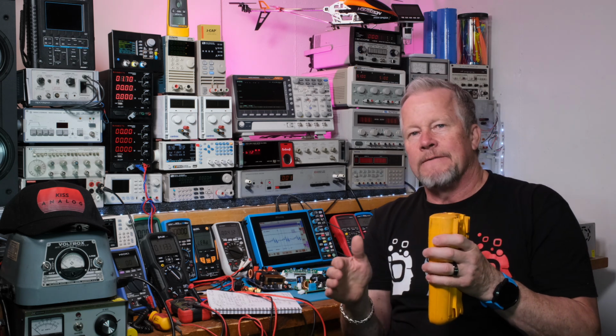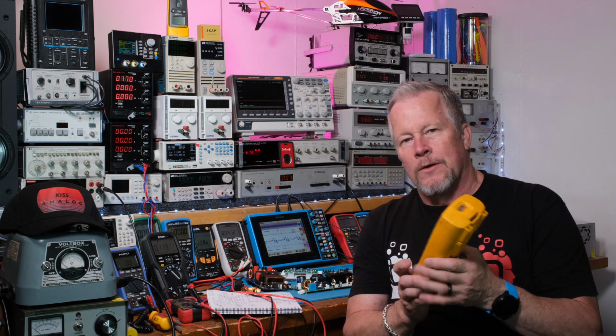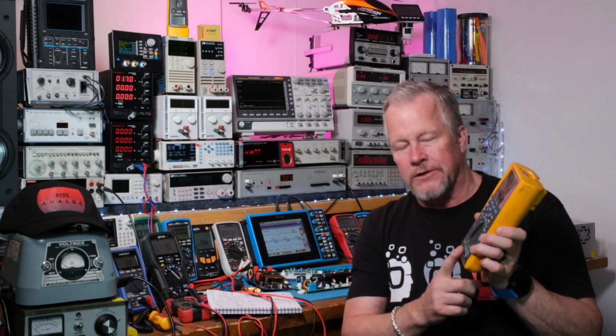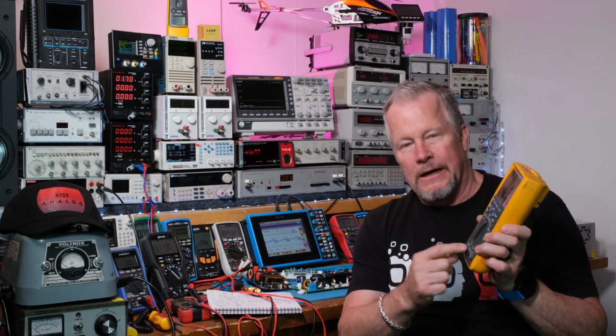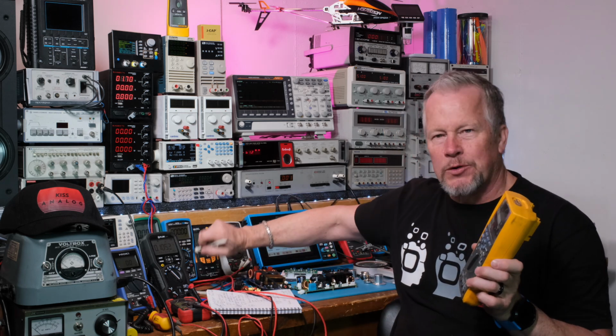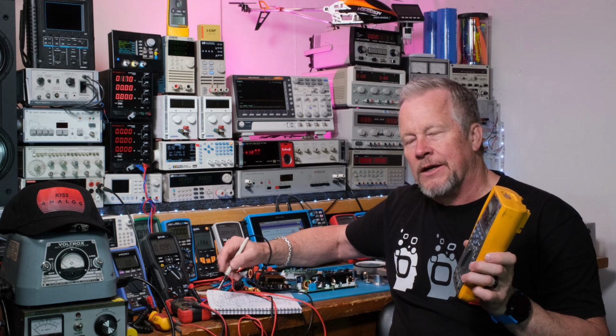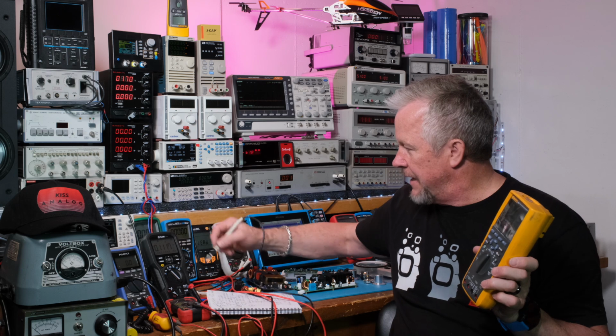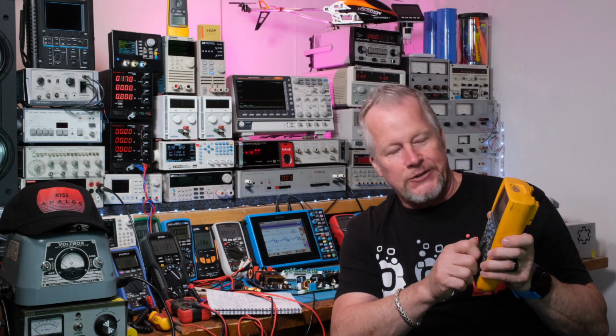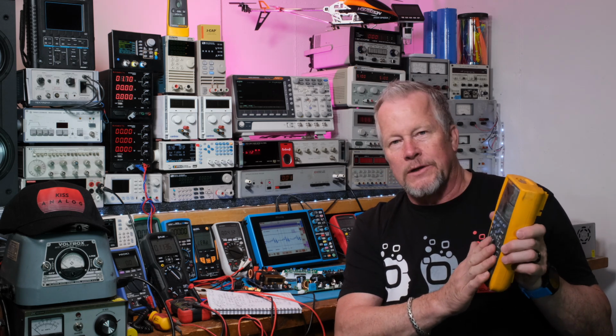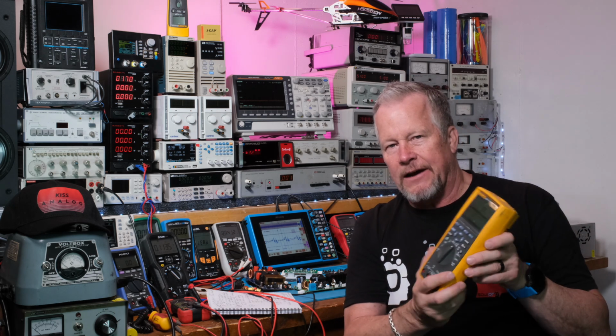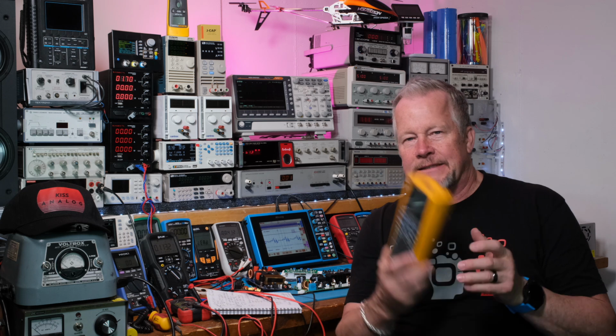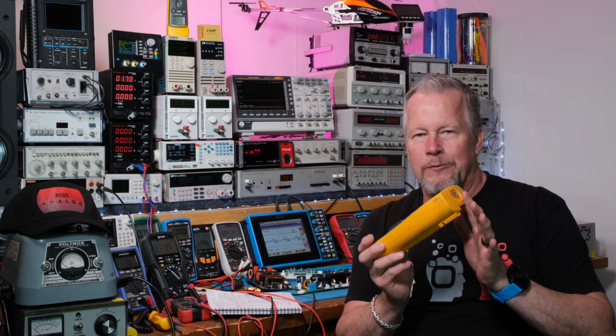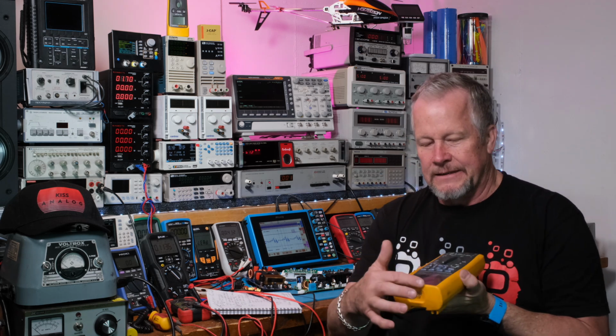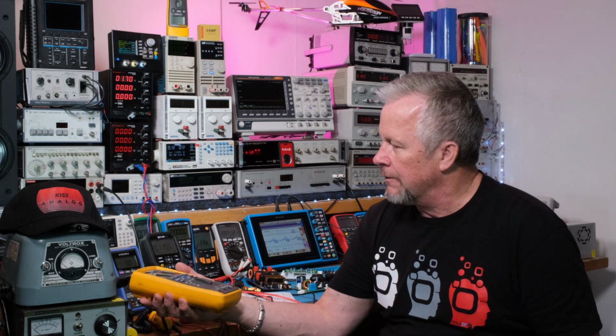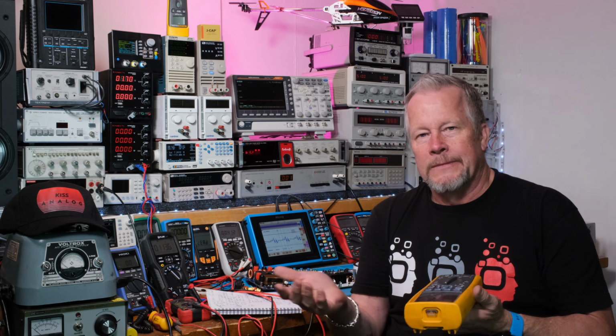Now, the Keysight, there's a few features it has. It has a square wave generator that actually puts out a signal. It has that extra little probe input that you can use for those smart probes, they're called remote probes, that have the little sensors, so you can say save, save, save. So it has that feature. It also has a counter feature. So besides looking at frequency, it has a frequency counter, so it'll act like a frequency counter. And like a lot of meters these days, again, this is a 15-year-old meter, so maybe they would have added some of these things, who knows? But it has the little non-contact voltage feature, so you can go up to a thing and go, yep, there's voltage there. So it has that feature too.